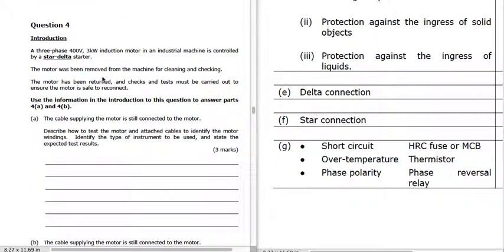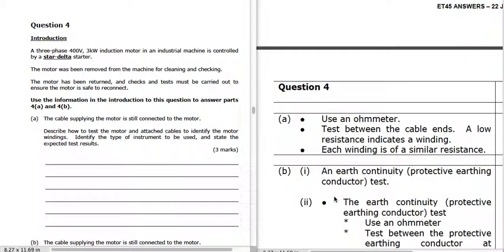Question 4: we've got a three-phase 400-volt 3-kilowatt induction motor with star-delta starting. To identify motor windings with the ends exposed, we use an ohmmeter and test between the cable ends in pairs, trying to find pairs by their low resistance. We're looking for three pairs of similar and low resistance.